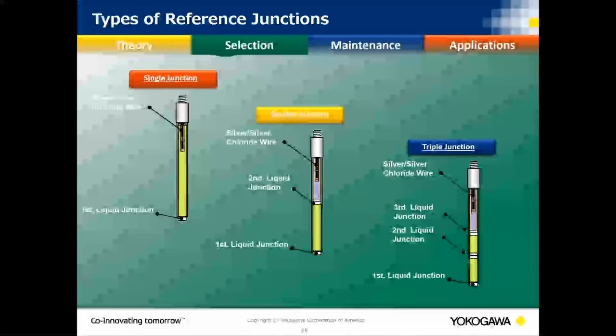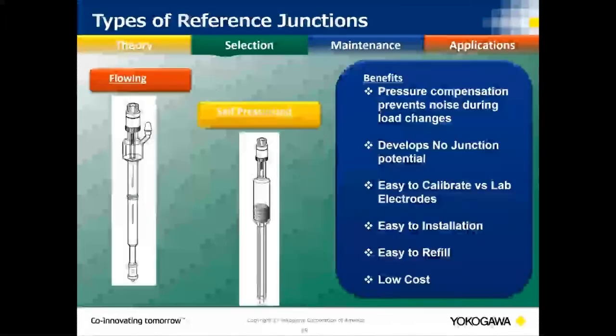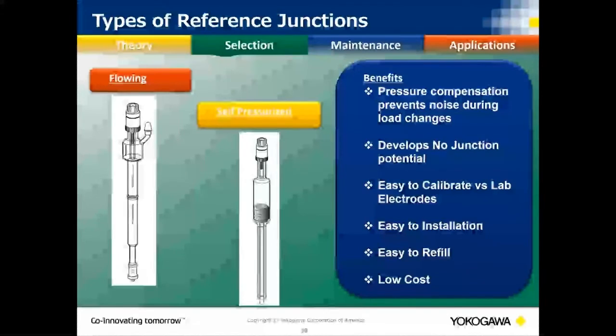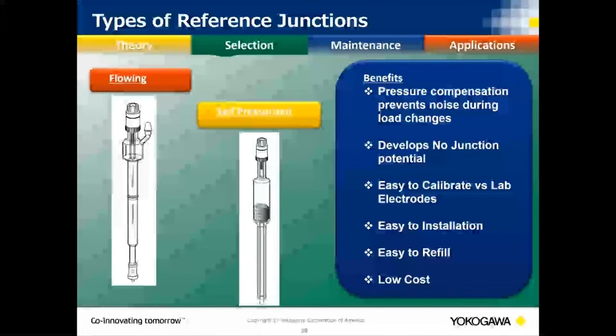You can also have single, double, or triple junctions. The more junctions, the longer the life of your probe, because the process has to attack through each junction before it can reach your reference pin. With a double junction the process must get through two, and with a triple junction, three before it can reach the reference electrode.